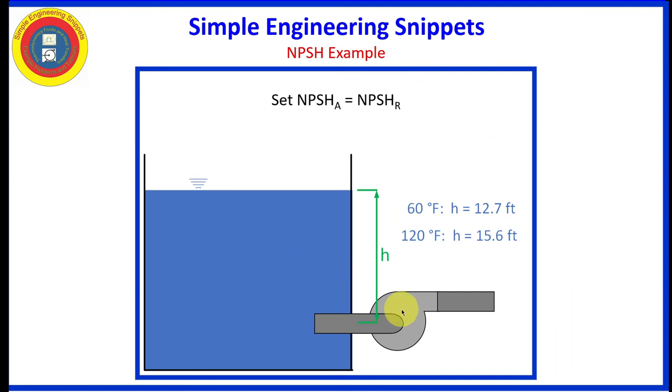So here is the final answer showing the new orientation of the pump that would be required. If it's 60 degree water, it needs to be 12.7 feet beneath the surface. And if it was 120 degrees Fahrenheit, it would need to be 15.6 feet beneath the surface. So I hope that was a good review and helpful. If so, please like and subscribe. Have a great day.